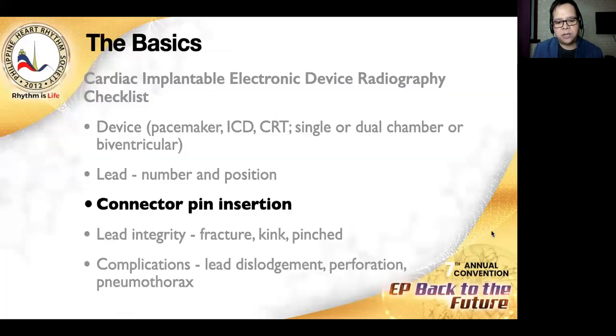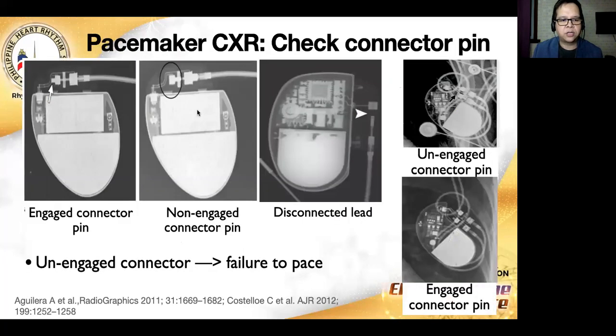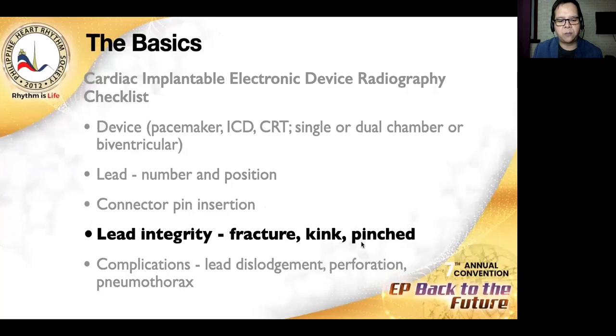Now, one of the problems that may be encountered leading to pacing issues is the insertion or engagement of the connector pin. So this is the connector pin. The connector pin of the device lead must be well seated in the so-called generator connector block. So in here, we see images of a non-engaged connector pin. And take note that a disconnected pin can lead to failure to pace. So these are pictures of an unengaged connector pin, and this was corrected eventually. So this will lead to pacing problems.